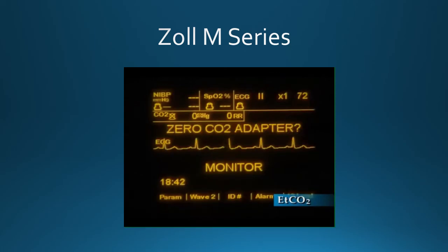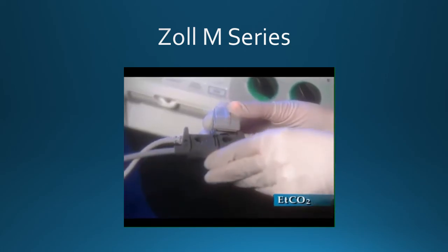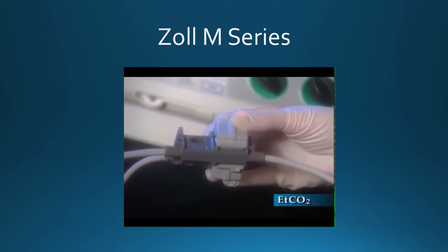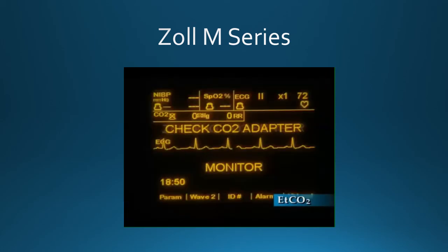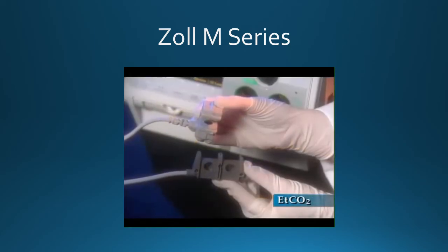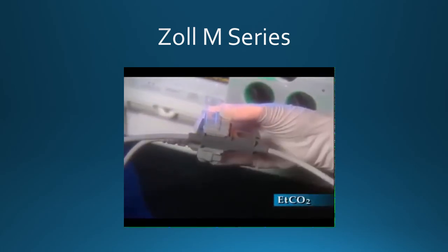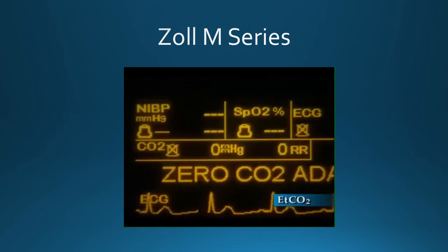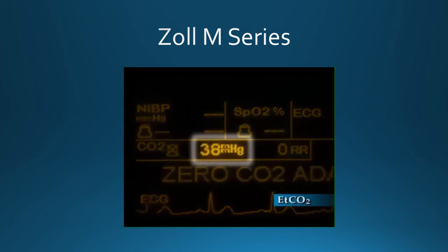The first time a particular capnostat sensor is connected to the M-Series, a zero CO2 sensor message will be displayed after the sensor is warmed up. This is only required when a capnostat is plugged into an M-Series for the first time. The same capnostat may be unplugged and replugged into the same M-Series without re-zeroing. Place the sensor on the zero cell, which is attached to the sensor cable. A zeroing CO2 sensor message will be displayed for about 15 seconds while the sensor is automatically zeroed. The sensor's zero calibration can be checked by placing the sensor on the reference cell. An EtCO2 value of 38 millimeters of mercury, plus or minus 2 millimeters of mercury, should be displayed.